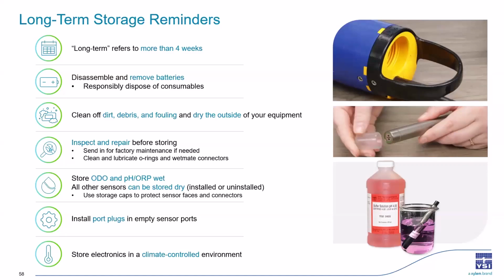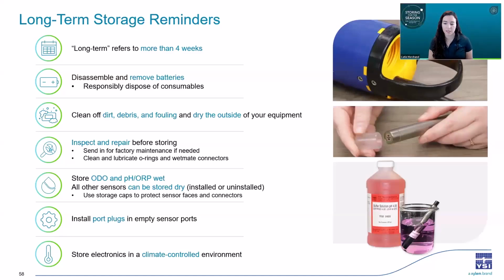For the sensors, store optical dissolved oxygen and pH or ORP sensors wet according to their instructions, and choose either wet or dry storage for your ISEs or ion selective electrodes. And then all other sensors can be stored dry. Use their storage caps to protect the sensor tips and the connectors if you have them, or install the sensor guard if they were left in your instrument. And if you remove sensors, put port plugs in the bulkhead of your instrument to protect the ports. And finally, store anything electronic in a climate-controlled environment.